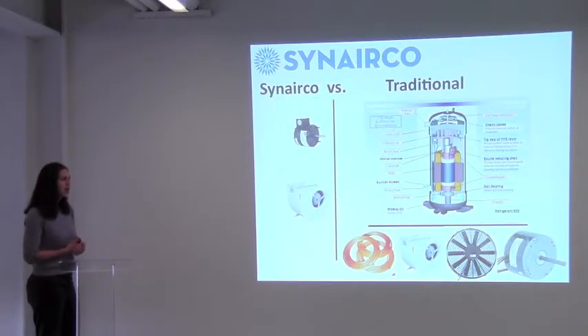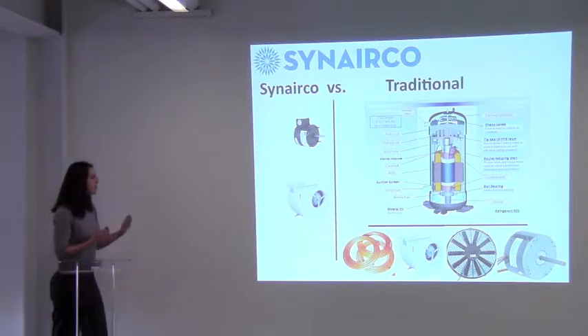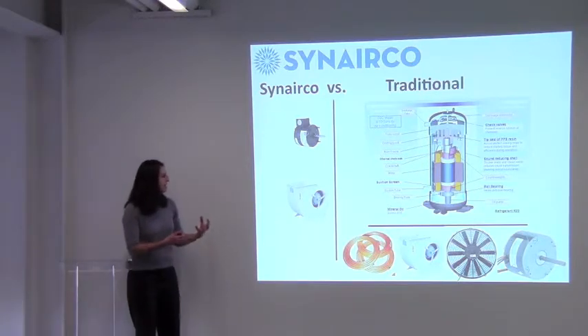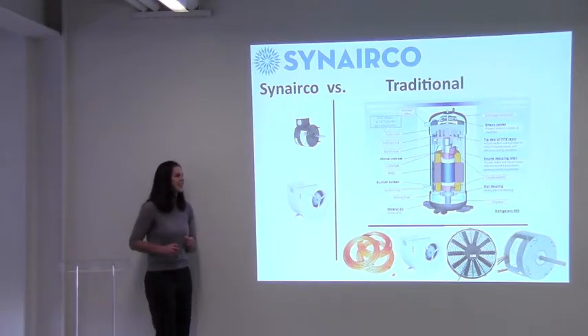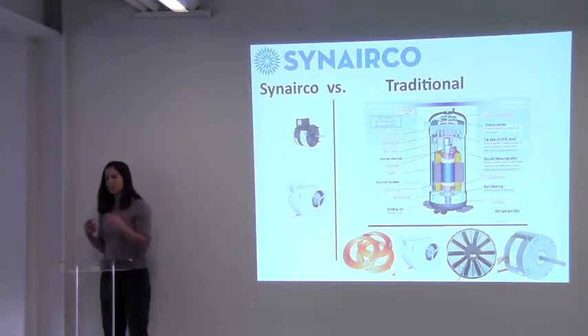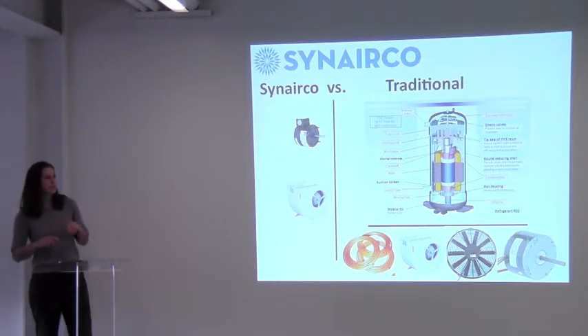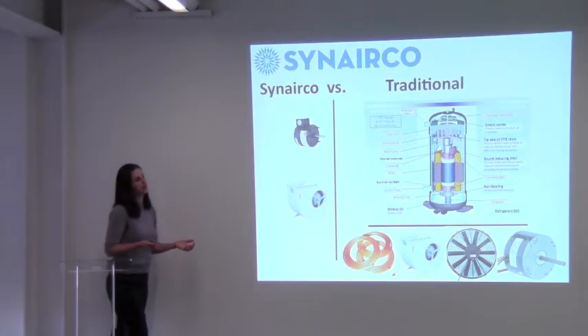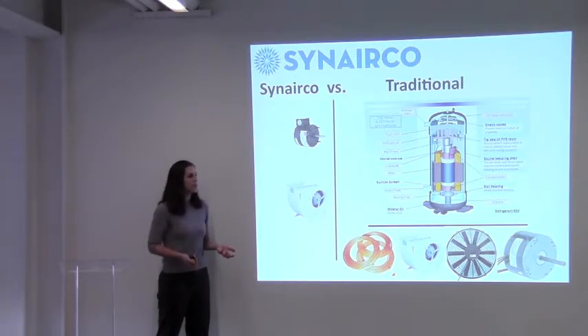The second part of the value of our unit—what's so brilliant about it—is inside the split airstream desiccant unit, there are only 2 moving parts: the supply fan, and a fractional horsepower motor. That's it. That's all you need to service.